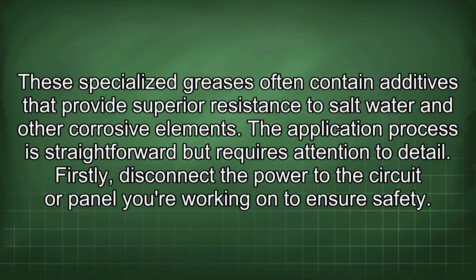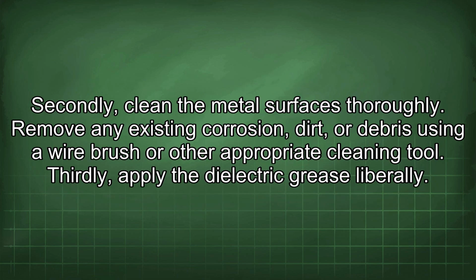The application process is straightforward but requires attention to detail. Firstly, disconnect the power to the circuit or panel you're working on to ensure safety. Secondly, clean the metal surfaces thoroughly. Remove any existing corrosion, dirt, or debris using a wire brush or other appropriate cleaning tool.